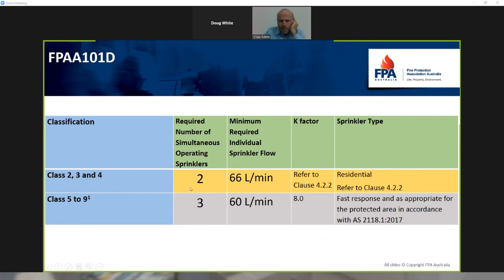This talks about the required numbers of sprinklers to operate. So in the class 2s and 3s and 4s, the residential parts, we need 2 sprinklers operating, each at 66 litres per minute. That extra little bit beyond 2118 part 5, which is only 50 litres a minute, is to make up for all of the domestic use that could be occurring at the time of a fire. The class 5 to 9 areas, the non-residential areas, are required to have 3 sprinklers operating at 60 litres a minute, and that's taken its lead from 2118 part 4 that talks about the non-residential areas of a part 4 building. It actually uses that same performance requirement.